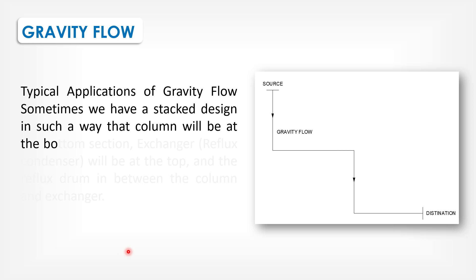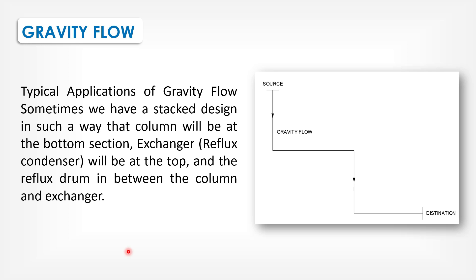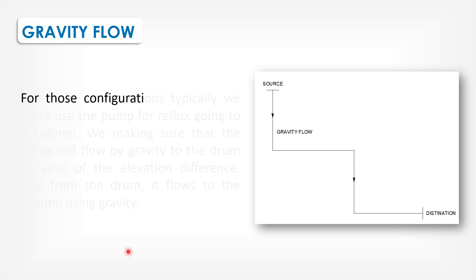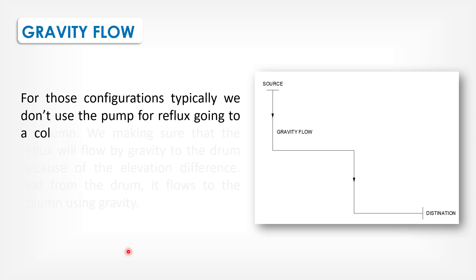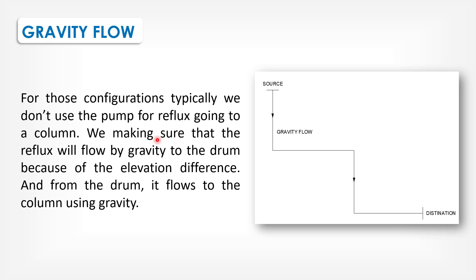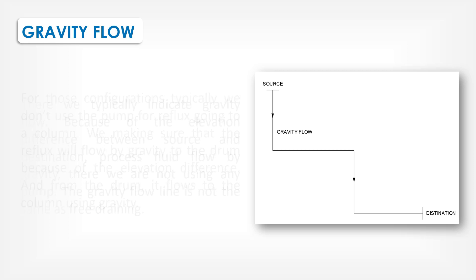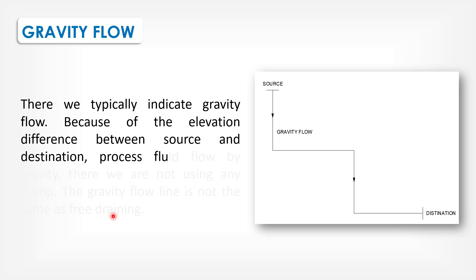For typical application of gravity flow, sometimes we have a stacked design in such a way that column will be at the bottom section, exchanger reflux condenser will be at the top, and the reflux drum in between the column and exchanger. For those configurations, typically, we don't use the pump for reflux going to the column. We are making sure that the reflux will flow by gravity to the drum because of the elevation difference. And from the drum, it flows to the column using gravity. There we typically indicate gravity flow because of the elevation difference between source and destination. Process flows by gravity. There we are not using any pump.